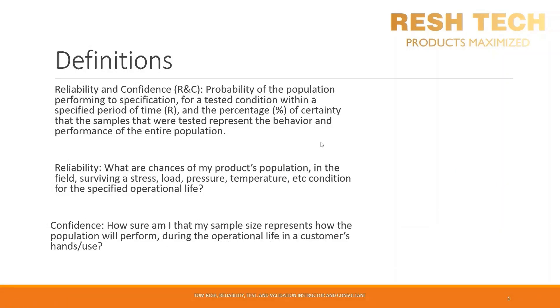Let's define reliability and confidence, which are key parameters in defining a sampling plan and are used primarily in design verification and validation sample size determination. Reliability and confidence is the probability of the population performing to specification for a tested condition within a specified period of time, and the percentage of certainty that the samples tested represent the behavior and performance of the entire population. In simpler terms: for reliability, what are the chances of my product's population in the field surviving a stress, load, pressure, temperature, or other condition for the specified operational life? With confidence, we ask how sure am I that my sample size represents how the population will perform during the operational life in a customer's hands?